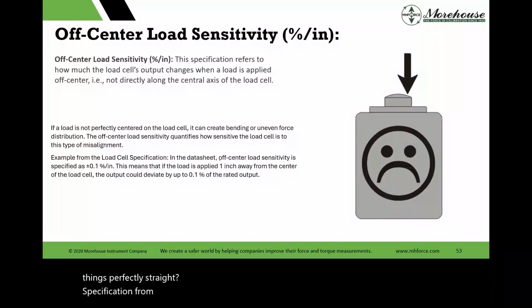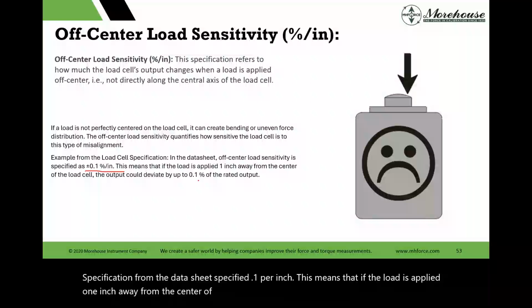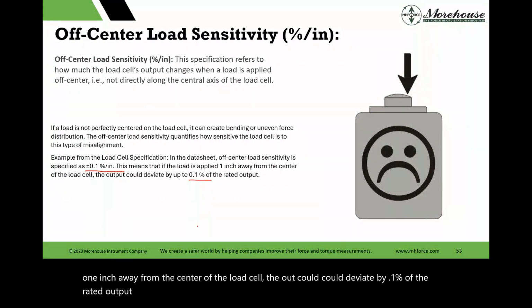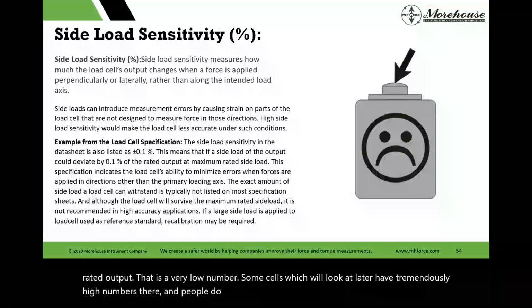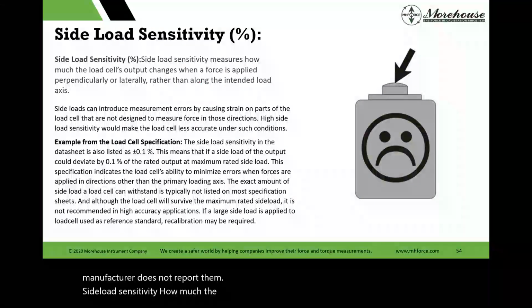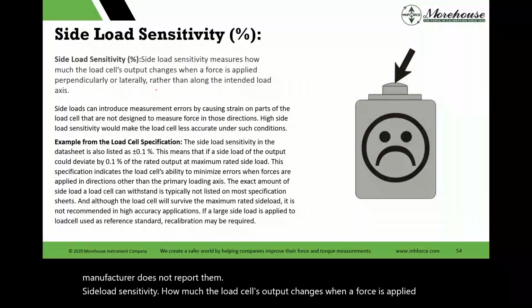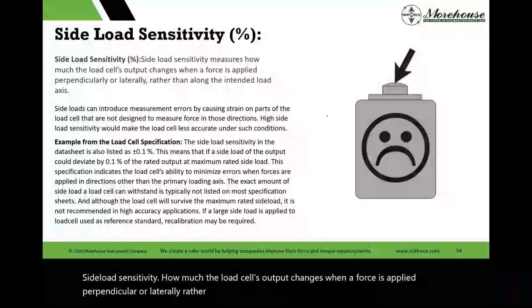The specification from the data sheet is 0.1% per inch. This means that if the load is applied 1 inch away from the center of the load cell, the output could deviate by 0.1% of the rated output. That is a very low number. Some cells, which we'll look at later, have tremendously high numbers there, and people do not pay attention to them, or the manufacturer does not report them. Side load sensitivity is how much the load cell's output changes when a force is applied perpendicular or laterally rather than along the intended load axis.